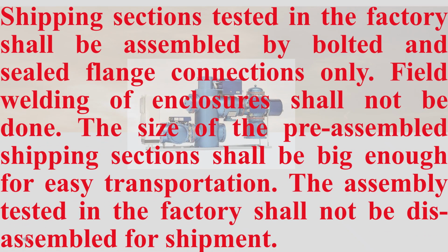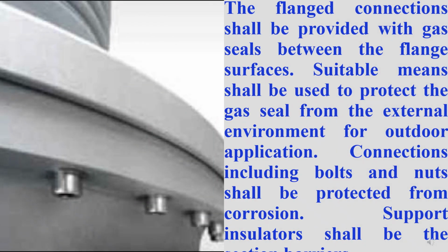Shipping sections tested in the factory shall be assembled by bolted and sealed flange connections only. Field welding of enclosures shall not be done. The size of the pre-assembled shipping sections shall be big enough for easy transportation. The assembly tested in the factory shall not be disassembled for the shipment. The flanged connections shall be provided with gas seals between the flange surfaces. Suitable means shall be used to protect the gas seal from the external environment for outdoor application. Connections including bolts and nuts shall be protected from corrosion.